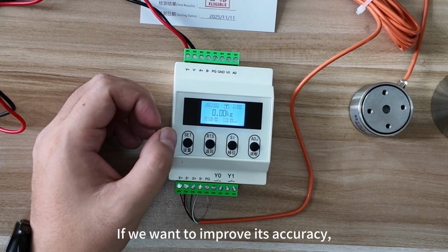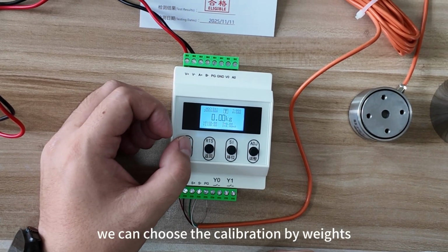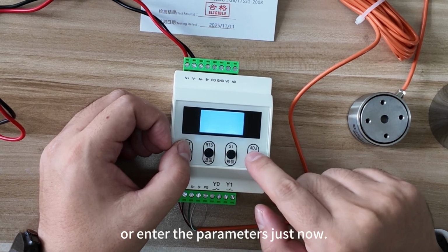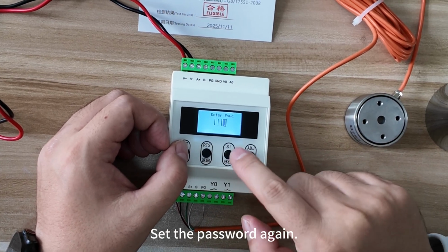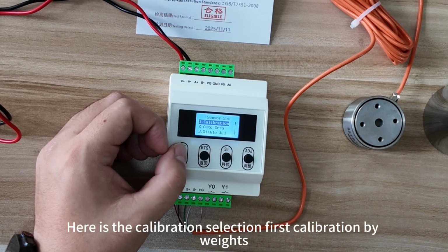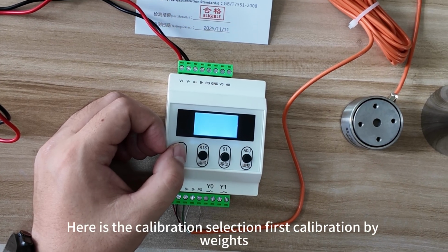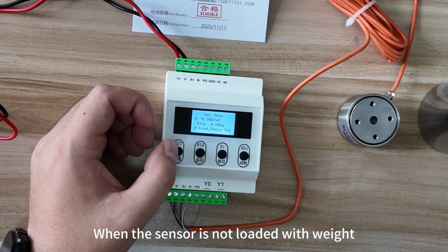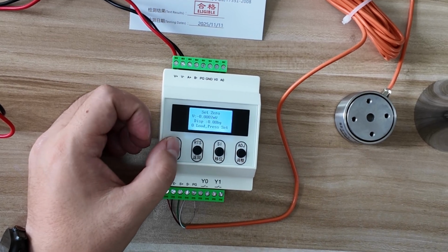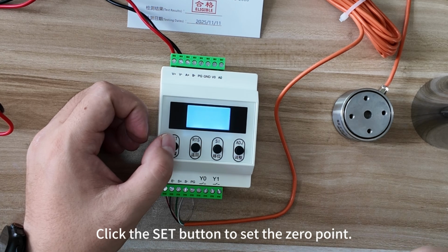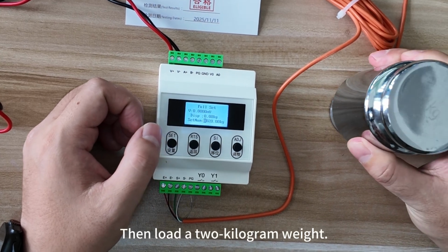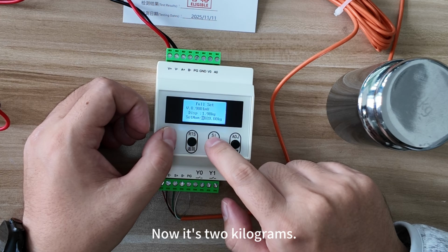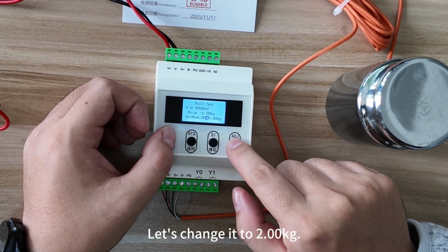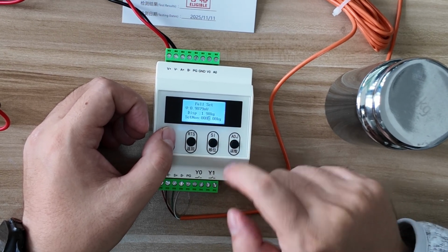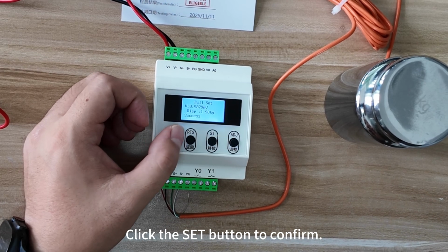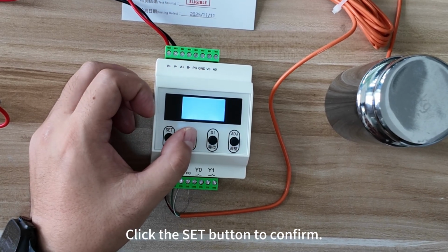If we want to improve its accuracy, we can choose the calibration by weights, or enter the parameters just now. Set the password again. Here is the calibration selection, first calibration by weights. When the sensor is not loaded with weight, click the SET button to set the 0 point. Then load a 2 kilogram weight. Now it's 2 kilograms. Let's change it to 2.0 kilograms. Click the SET button to confirm.